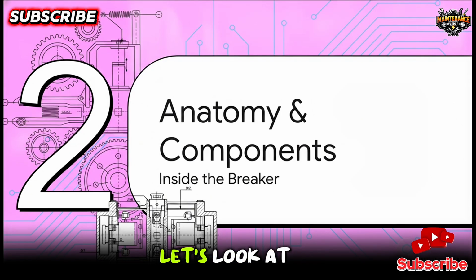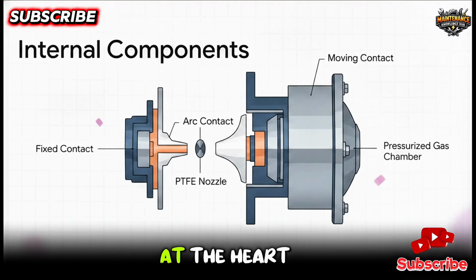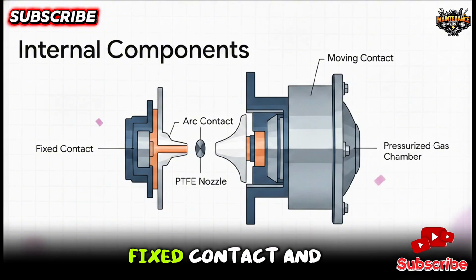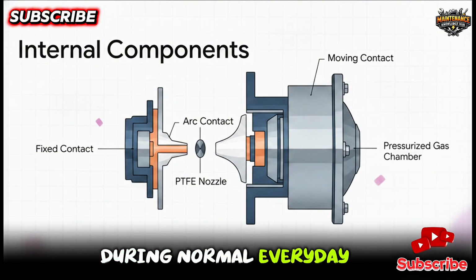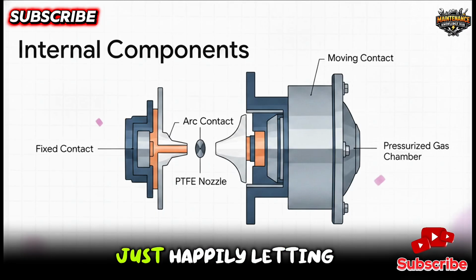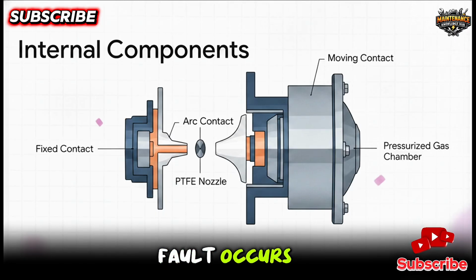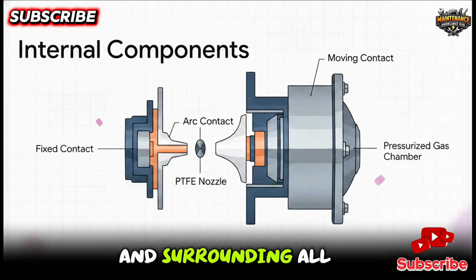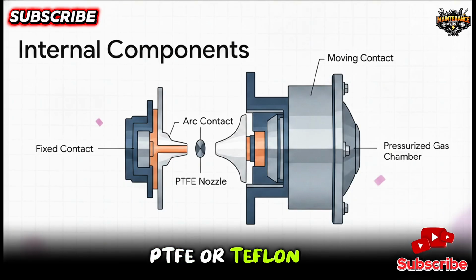Moving right along to Section 2, let's look at the anatomy and main components. Right at the heart of the breaker's interrupting chamber, we have the fixed contact and the moving contact. During normal, everyday operation, these guys are clamped tightly together, just happily letting the current flow. But when a fault occurs, the operating mechanism mechanically yanks that moving contact away. And here is the absolute genius part. There is a specific, dedicated piece called the arc contact. As the main contacts separate, this arc contact is designed to carry the electrical arc initially. It takes the full brunt of that terrifying heat, so the main, primary contacts don't get melted and destroyed. And surrounding all this is a PTFE, or Teflon, nozzle, housed right inside that highly pressurized SF₆ gas chamber.